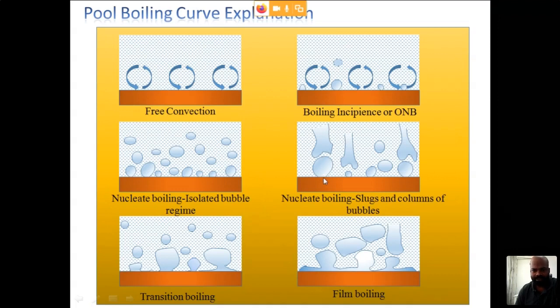As conditions progress, vertical and horizontal coalescence of bubbles takes place, with bubbles merging to form slugs. When this becomes severe enough, vapor completely covers the surface, forming a vapor layer between the liquid and solid surface that restricts heat transfer from solid to liquid. This causes the surface temperature to rise very high, and the surface can suddenly burn or fail. This condition is called critical heat flux, meaning the system should not be operated at or above that point.